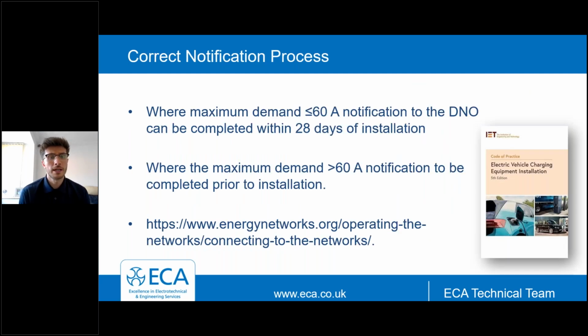Okay. So the next point we're going to look at is the correct notification process. And again, this is something that you need to look at doing as part of your pre-work survey, prior to actually carrying the work out. So when the maximum demand is less than or equal to 60 amps, notification to the DNO can be completed within 28 days of installation. So if, following the additional demand of your EV charge point, the demand is still going to sit below 60 amps, you can install the EV charging equipment and notify the DNO within 28 days of that installation being complete.